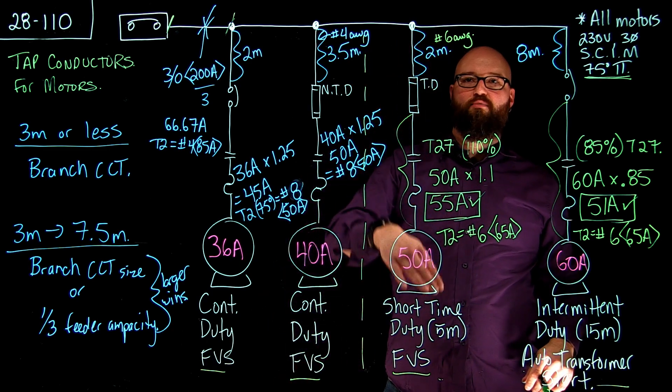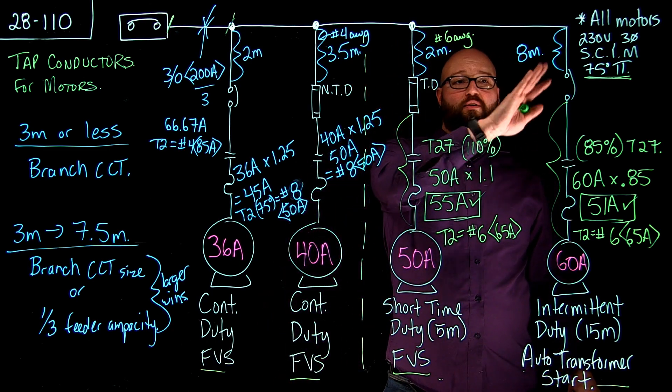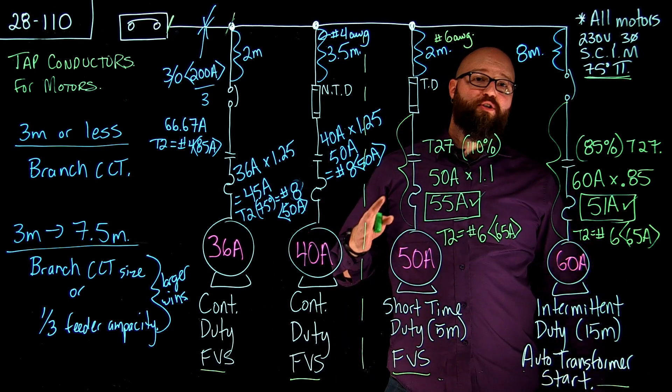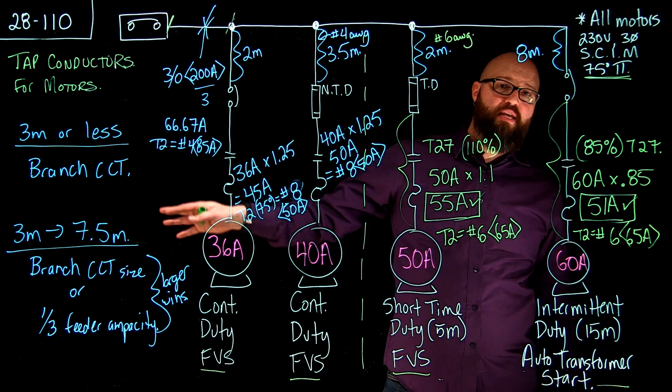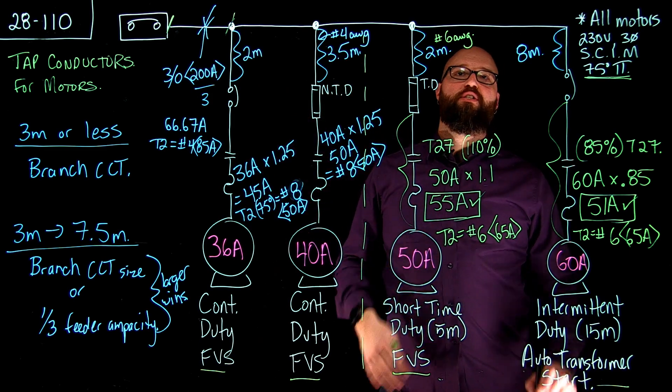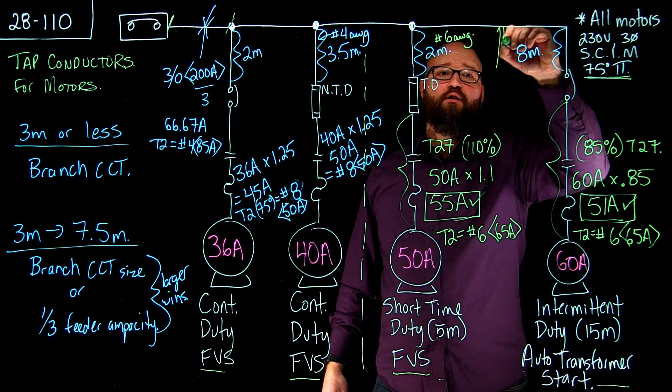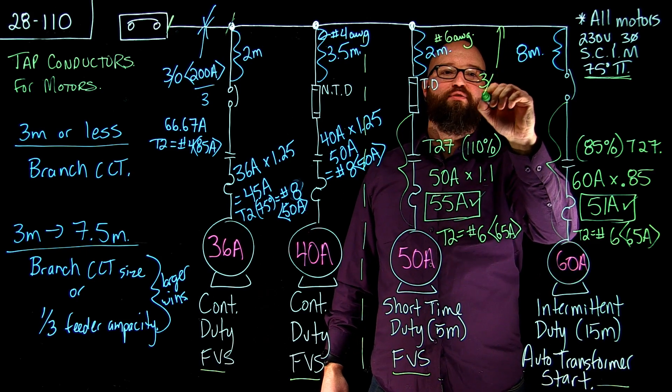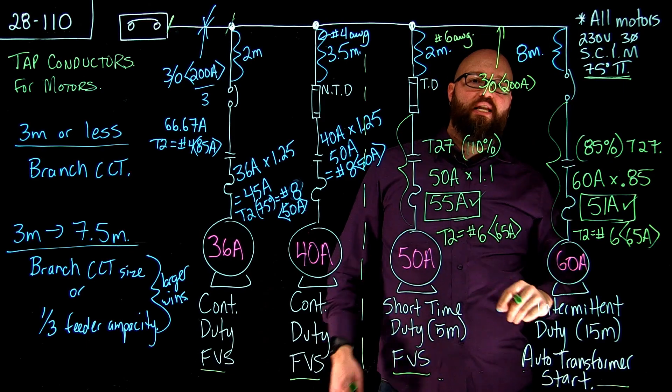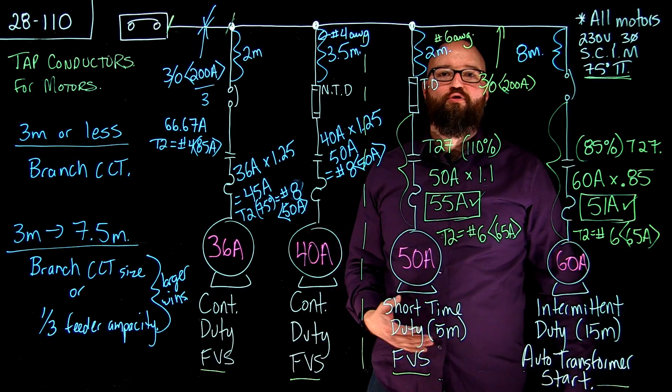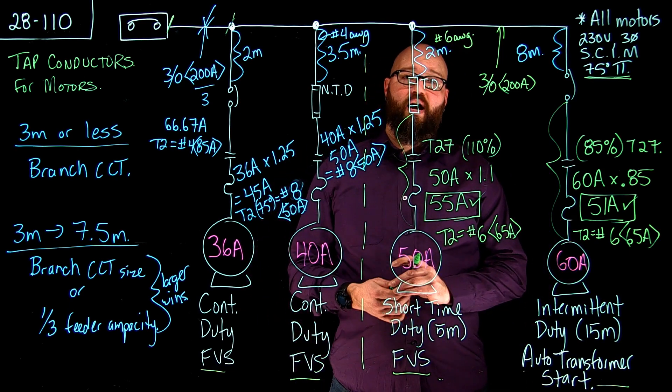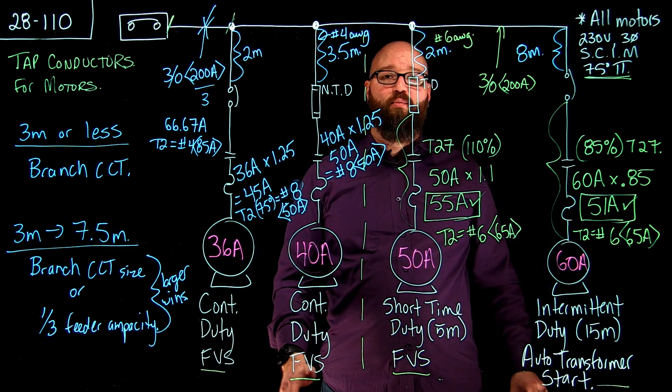From here to here I'm okay to get away with a number 6 from here to here. I'm okay to get away with a number 6 as well. Now we're 8 meters on our tap on this particular installation which means that I can no longer apply the tap conductors from 28110. I can't apply those rules. I would actually see this conductor would be equal to I would have a 3-0 good for 200 amps because I exceed that 7.5 meters. I'm not allowed to apply those exceptions in that case. So hopefully this has helped and we'll see you next time. Thanks for watching.